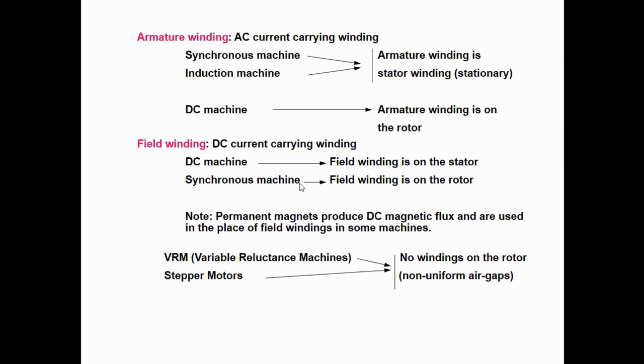If you ask me why, you can figure it out with a little common sense. In a DC machine, you need to take only two output terminals to collect the voltage if you consider the generator configuration. However, in a synchronous generator, you need at least three terminals, or in some cases six terminals. If you go on connecting so many brushes through slip rings or any other mechanism, it will increase the chance of sparking, wear and tear and other losses at your brush end.